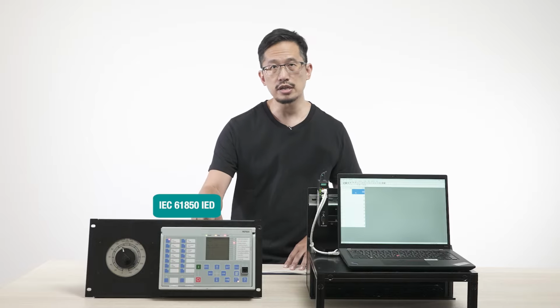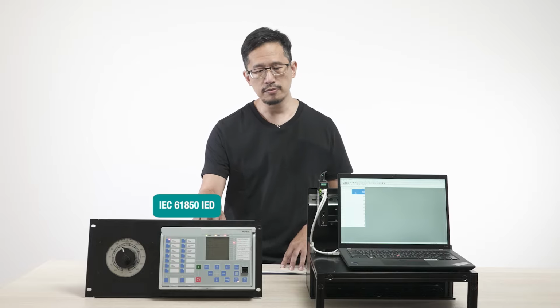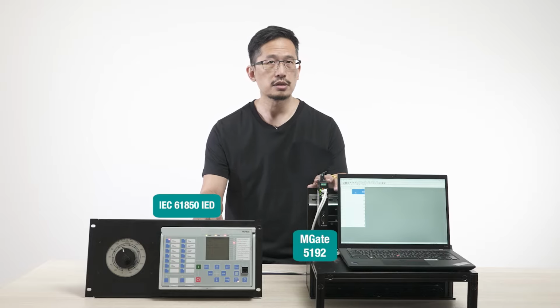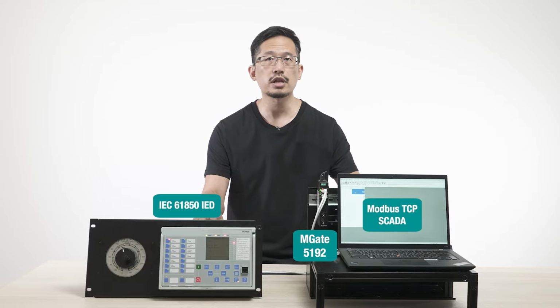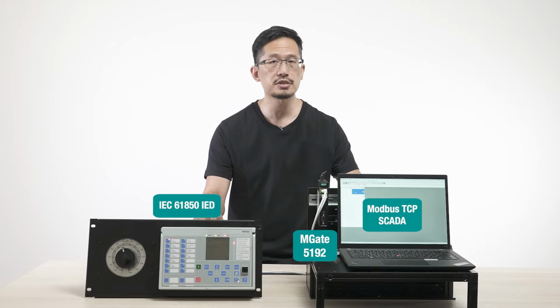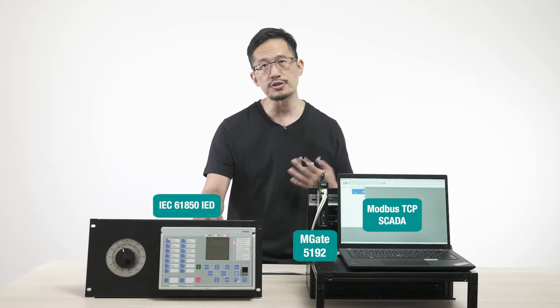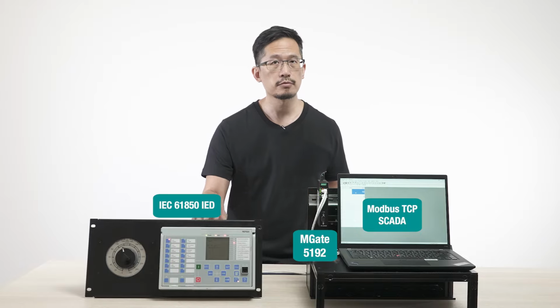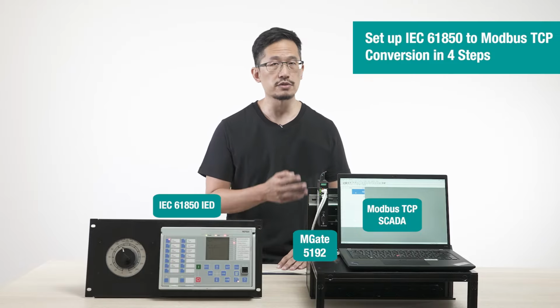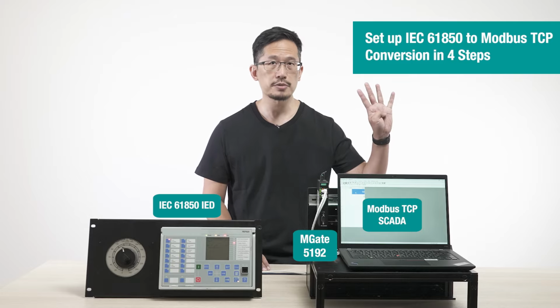So we have our IED, which runs IEC 61850, and we've connected it to our MGate. And our MGate is connected to a laptop that's running a Modbus TCP simulator, which we're using to represent our Modbus TCP SCADA. I'm going to show you how to configure this conversion in just 4 steps.